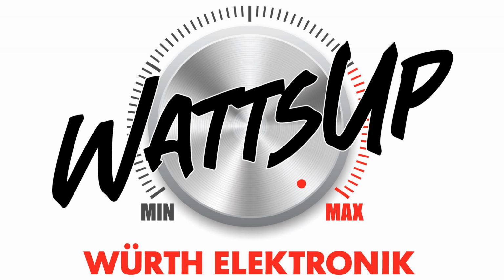The interference level, or V sub diff, can be defined in this equation: V sub diff equals 20 log times V sub ripple divided by 1 microvolt, multiplied by decibels microvolt. So if this equation is transformed, the measured interference voltage, or V sub ripple, can be determined as V sub ripple equals 10 to the power of V sub diff over 20, multiplied by 1 microvolt, which equals 10 to the power of 128 over 20 multiplied by 1 microvolt.